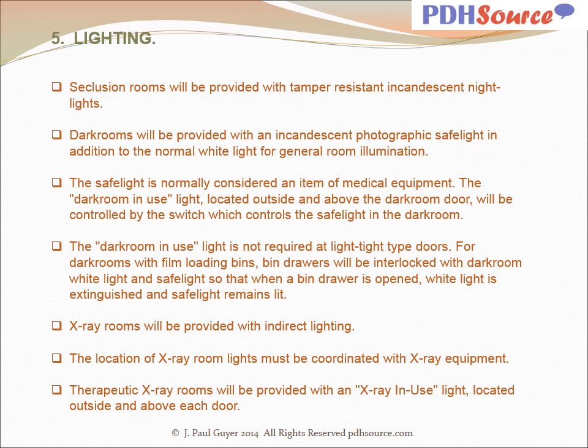For darkrooms with film loading bins, bin drawers will be interlocked with darkroom white light and safe light so that when a bin drawer is opened, white light is extinguished and safe light remains lit. X-ray rooms will be provided with indirect lighting. The location of X-ray room lights must be coordinated with X-ray equipment. Therapeutic X-ray rooms will be provided with an X-ray in use light located outside and above each door.